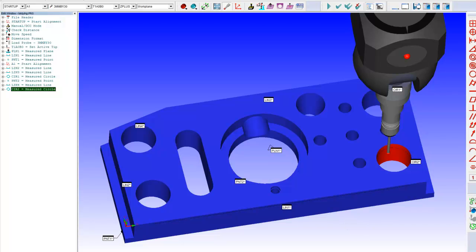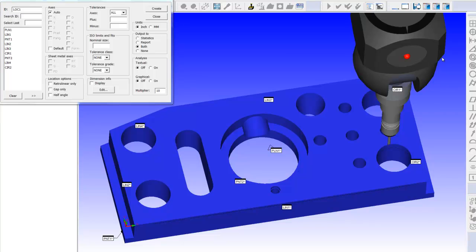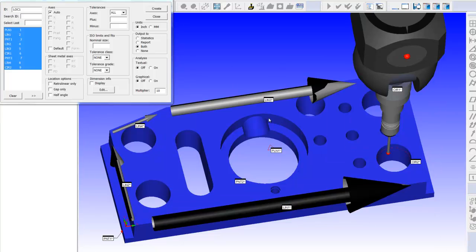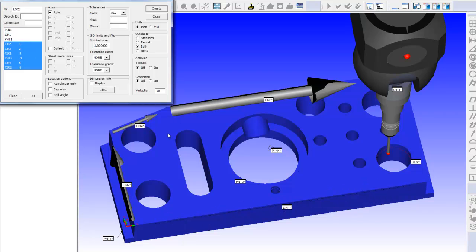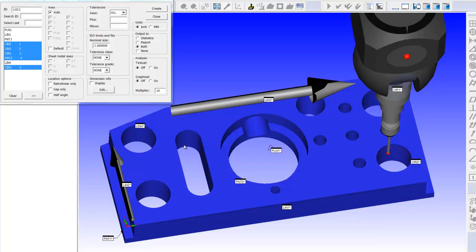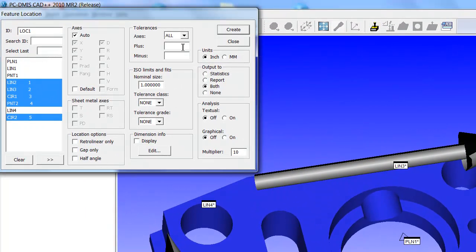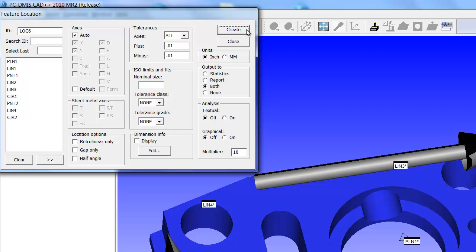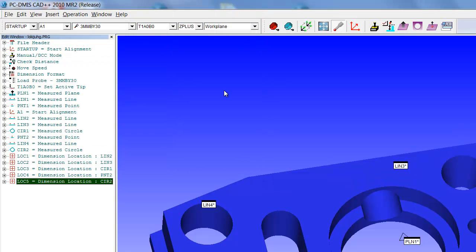Okay, so we've measured a bunch of different kinds of features. We're going to now go and dimension that stuff. Let's go to my dimension toolbars here on the right. I've got every possible dimension you can think of. Location, true position, distance, also have profile and run out. For this example, we're going to do a location. And we're going to pick everything on the screen. Notice what it does here. It allows me to graphically select the features on the graphics, so I don't have to remember the feature names. I can then go tell it to not report certain features, again, by clicking in the window with a list of features or by clicking on the graphic, either way. I can go put in a generic tolerance and say, go do that. What PCDMIS did was it just added those five dimensions automatically.